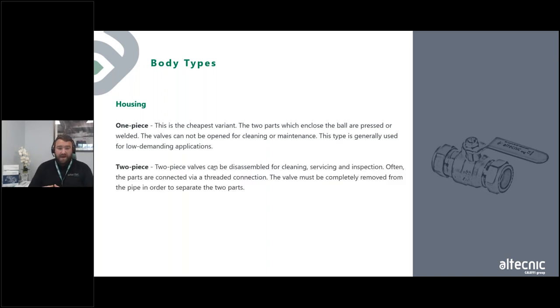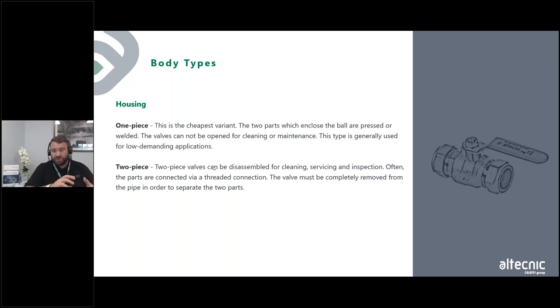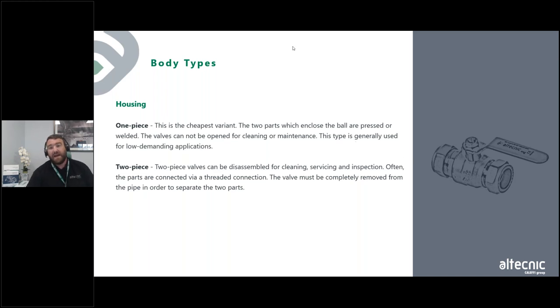Moving on, the two-piece valve is probably the most common valve we see in our sector. A two-piece valve can be disassembled for cleaning, servicing, and inspection — the parts are often connected via a threaded connection. The valve must be completely removed from the pipeline to separate the two parts. You have a main body, the ball is inserted, and then a secondary part is screwed together with two ball valve seats holding the ball in place. The image on the right-hand side here shows a two-piece ball valve.